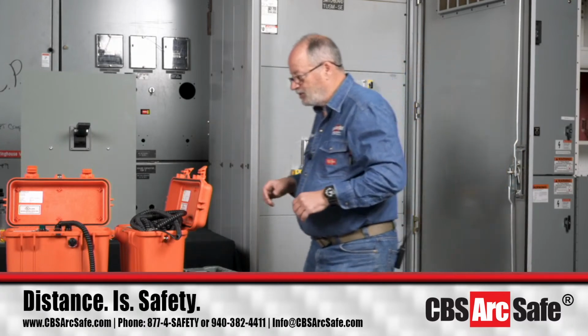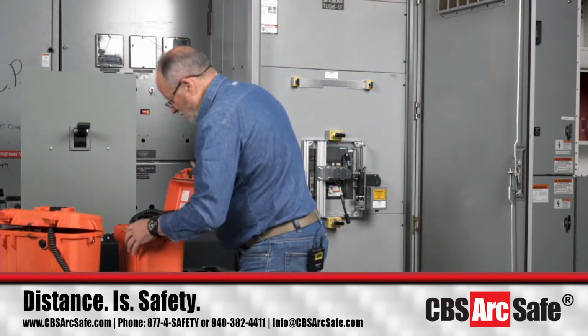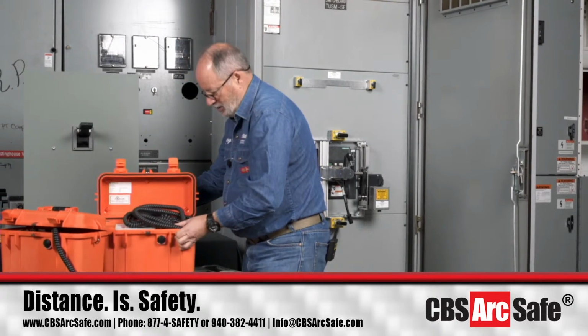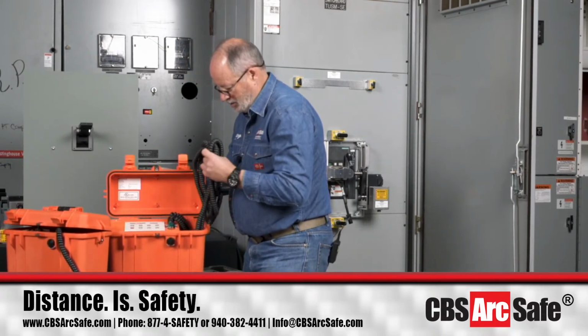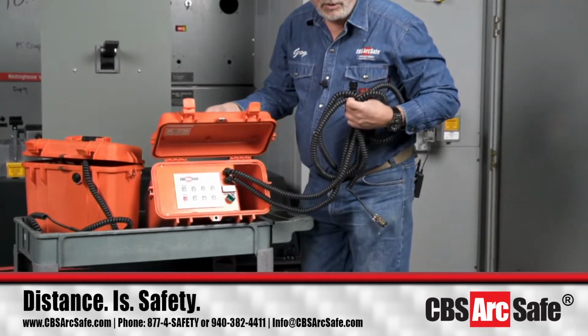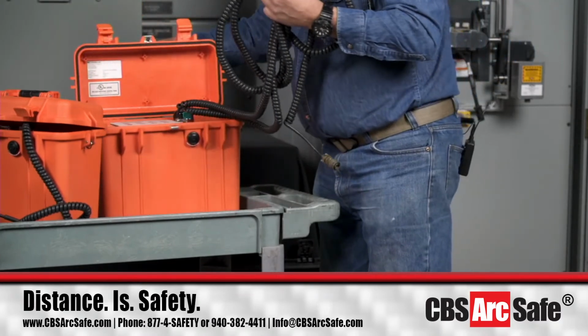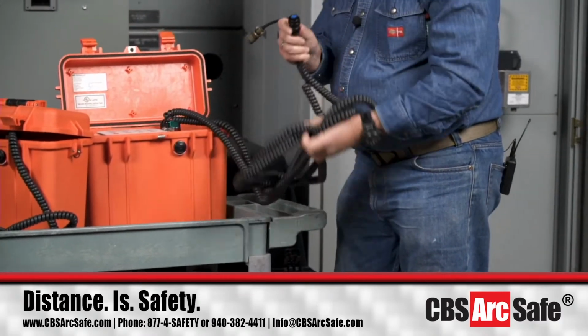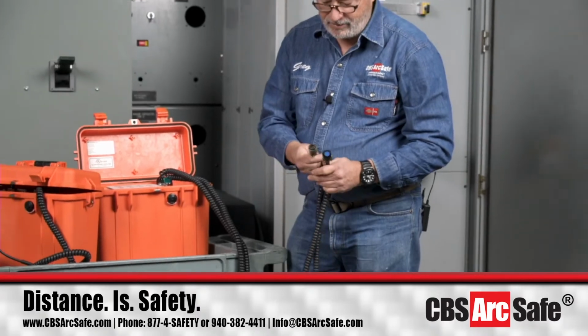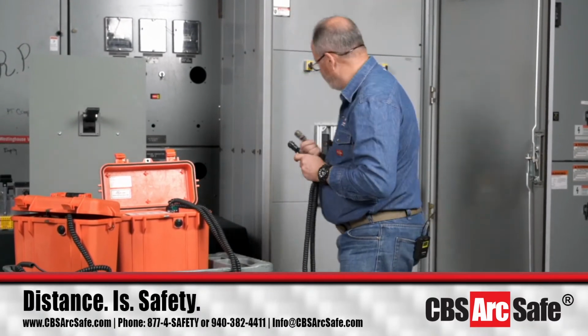Now this one, because it's going to be charge, close, and trip, we'll use the RSO 3D. All right. This is the difference as far as it's set up for charge, close, and trip operations compared to the RSO 1. It uses 2 cords, one for the charging motor and one for the close and trip solenoids.